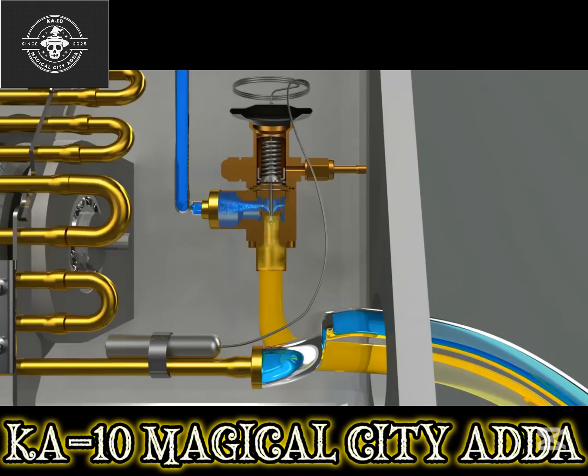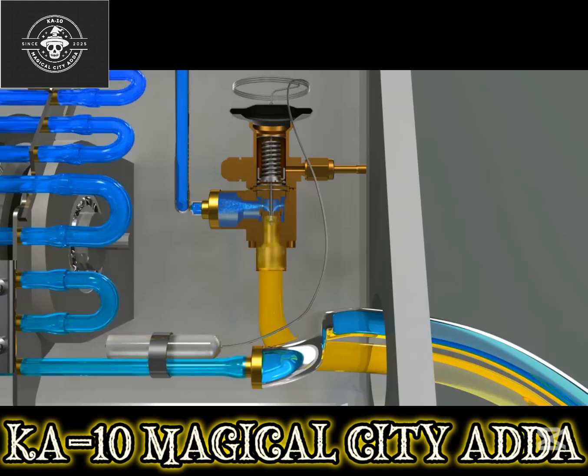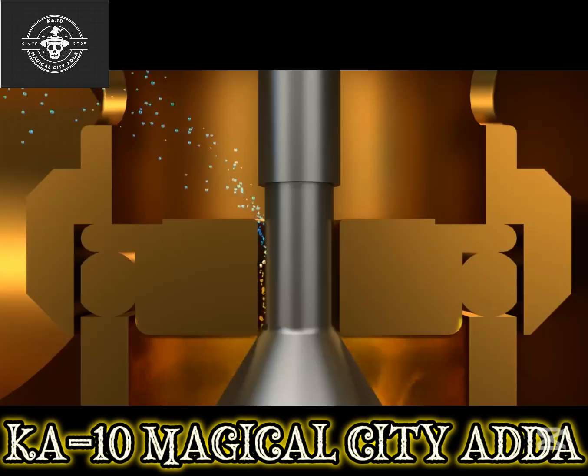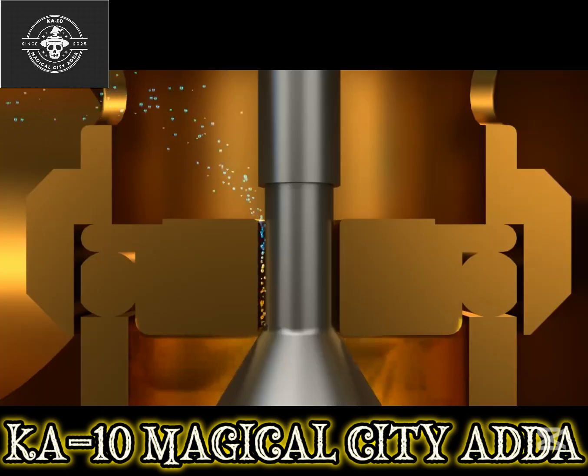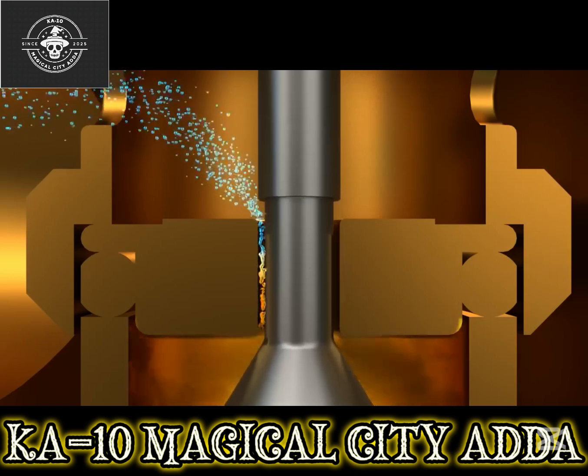The expansion valve is connected to a temperature sensing bulb that detects heat. The bulb is installed at the exit of an evaporator and detects temperature. Inside the bulb is fluid sensitive to temperature changes, and as the temperature at the exit of an evaporator rises, the gas pressure rises, which in turn presses on a spring to send more refrigerant to the evaporator.